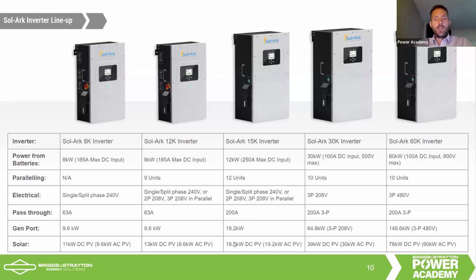if you use a transfer switch with a generator. And then on the DC side of things, you could bring in just under 20 kilowatts of DC solar. If you use the gen port for AC coupled solar, you can bring in 19 kilowatts of AC coupled solar on the AC side. The AC and the DC solar are somewhat independent. The AC bus is the limitation on the AC side on the gen port, and the DC bus is your limitation on the DC side. So you could bring in, let's say, 15 kilowatts of DC and couple in another 10 kilowatts of AC that you might already have on the roof for the 15K.